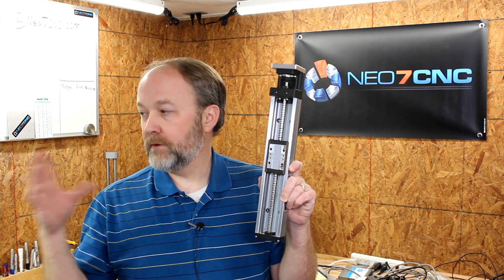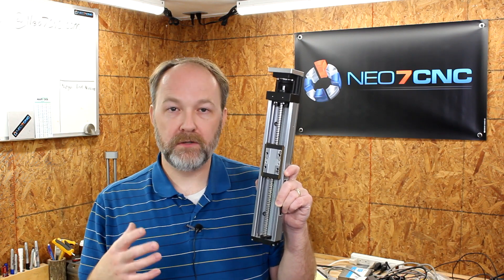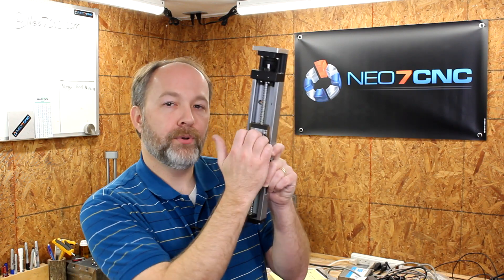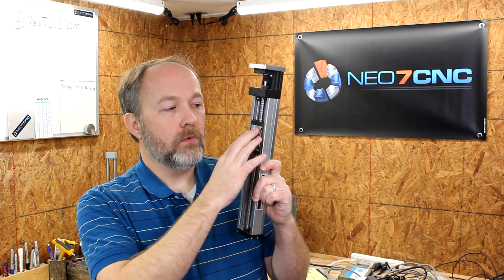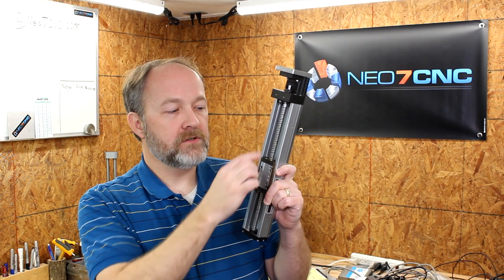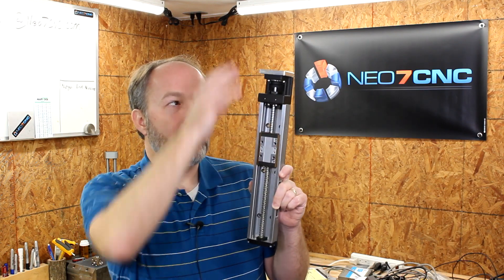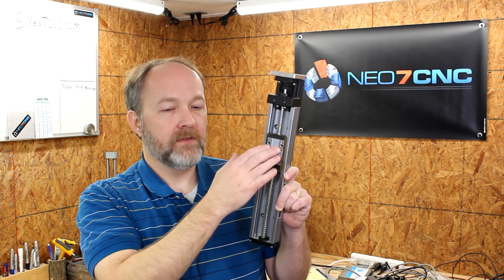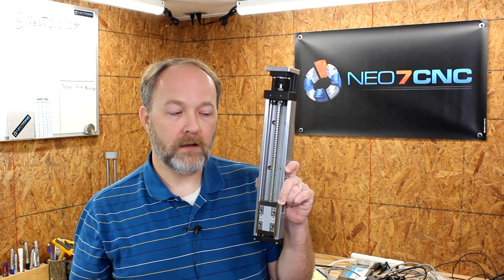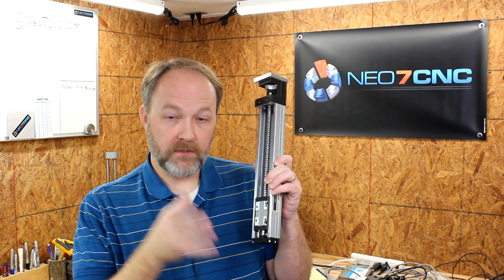I have weighed the brackets and the back plate and the spindle all together. That's about 16 pounds of weight pulling down on this. So even with the mechanical advantage of this finer pitch ball screw, if this motor loses power and it errors out, this is going to drop like a sack of rocks.